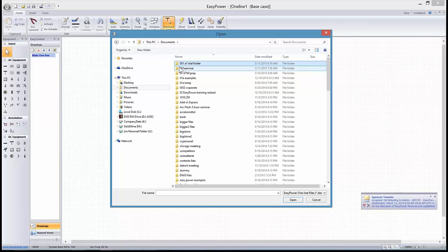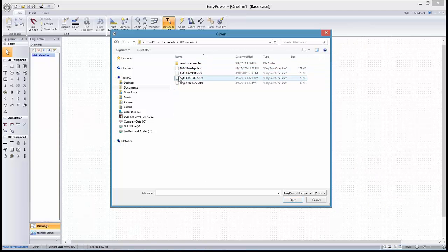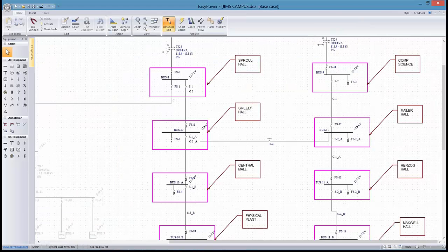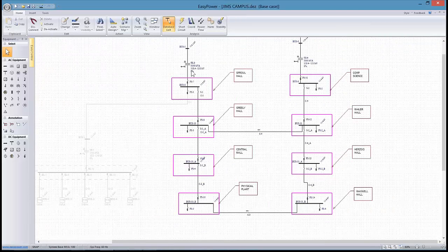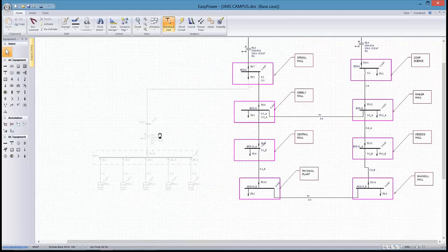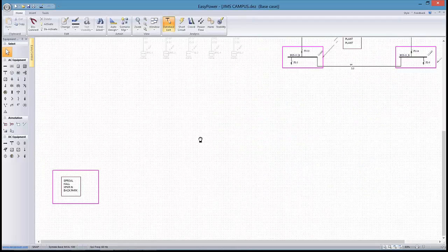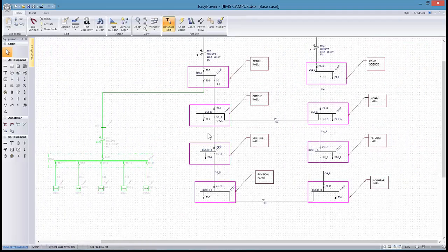What we're looking for is, for instance, let's say we have a ring set up, and in this case our medium voltage is distributed in a closed ring, and our ultimate distribution panels and subsystems will be much better illustrated if I can isolate them and then put them down in a section of the one line. So to do something like this, after I've walked through and considered, okay, this will allow me to control where my medium voltage is distributed.